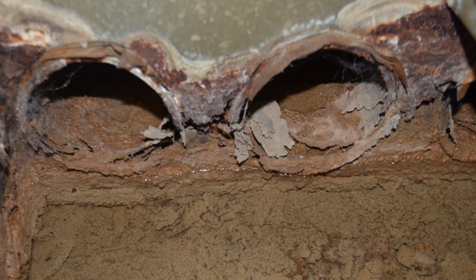After looking at the ducts and the rotted plenum, I was hoping we could dry the basement or the slab out, and not have her go up to the ceiling and flip the furnace around to put the heating system through the ceiling. But from the amount of deterioration in that plenum, it doesn't look too promising.